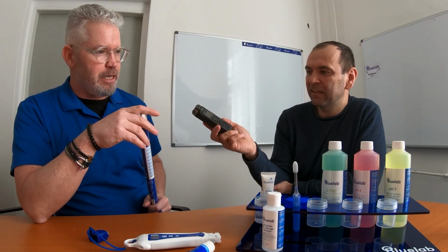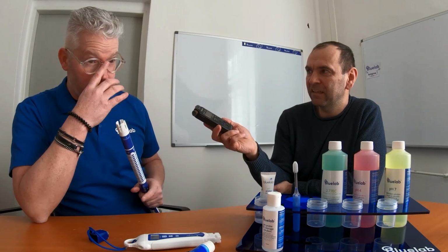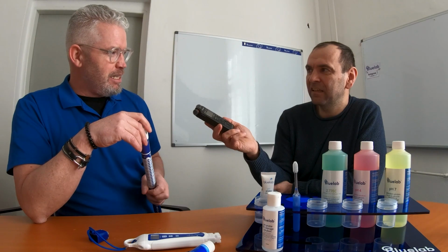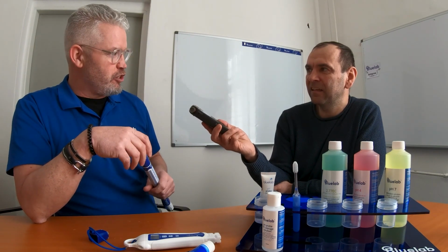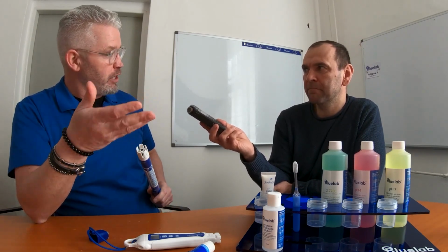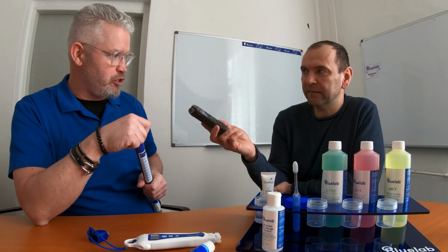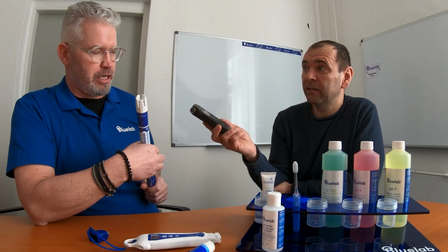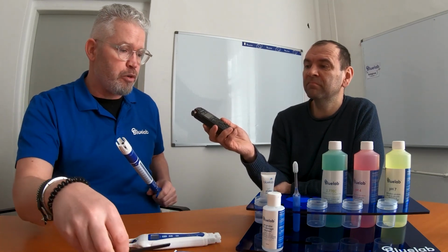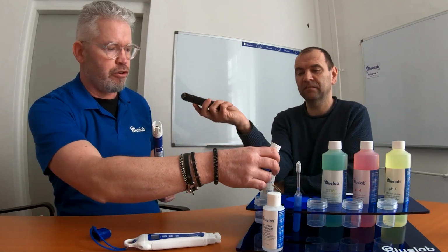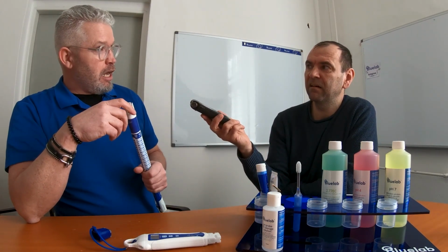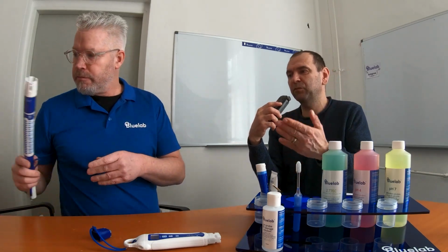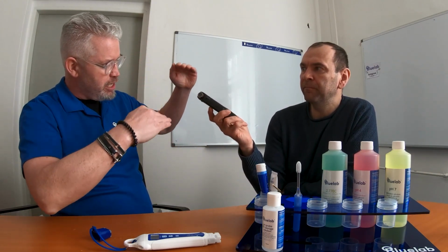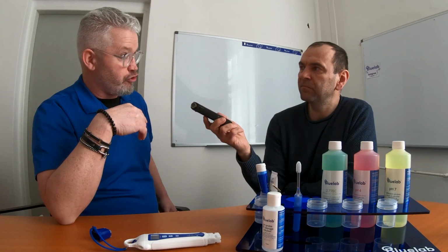If you have an EC pen or sensor, and it says I need calibration, actually, the reason why you need to calibrate it is that you need to compensate for the dirt. We prefer to clean it instead of compensating for the dirt. That's what you actually do with EC sensors and pens if you need to calibrate them. So cleaning is what we actually recommend, because that makes sure your EC reading is accurate. Okay, so I saw that I have to calibrate it because something is changing inside. So it's only dirt. Yeah, that's only dirt. For pH, yes, it is changing. The slope is changing, and you want to correct it for pH. EC, it's just dirt compensation.